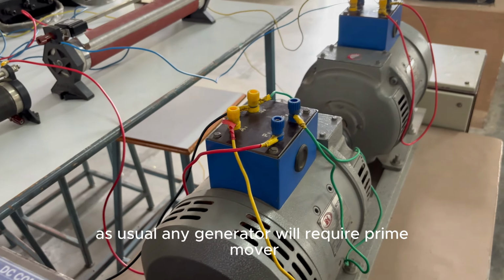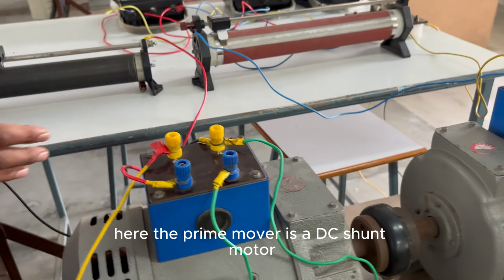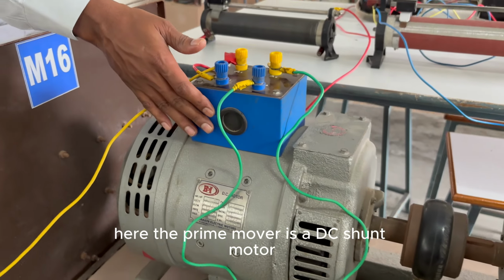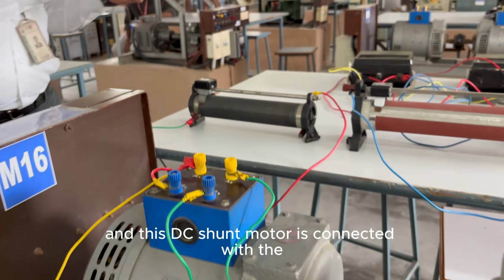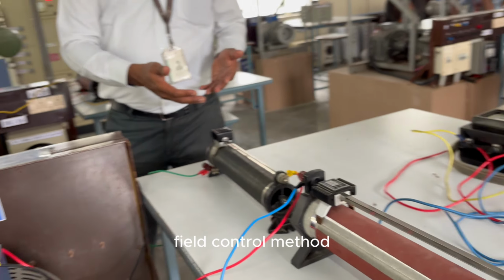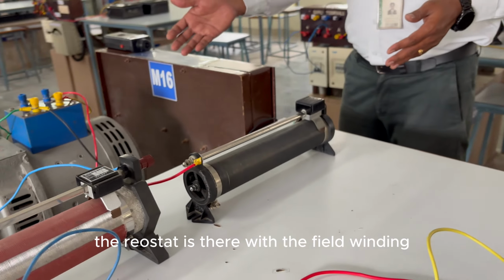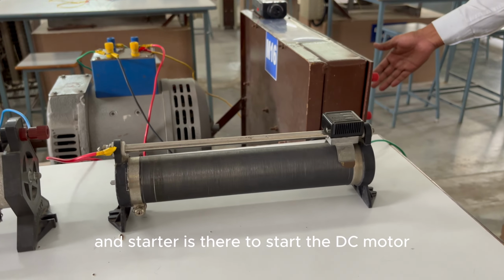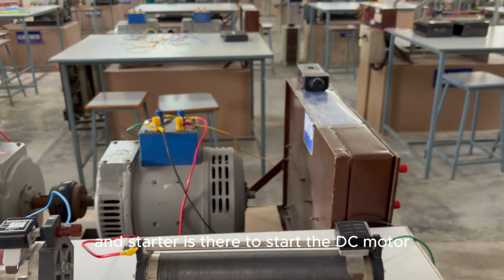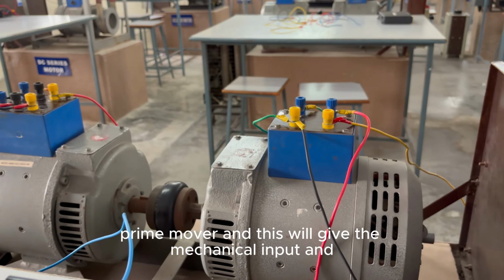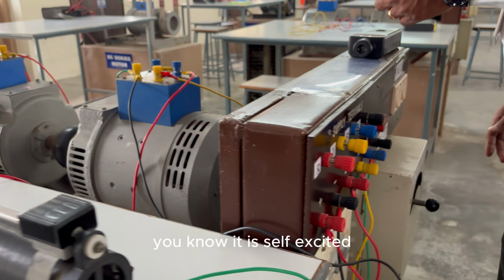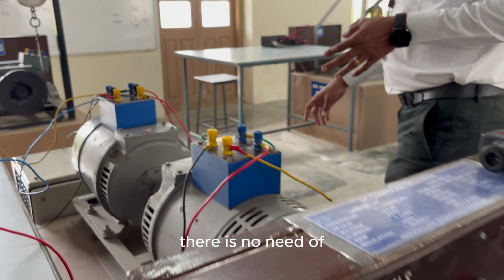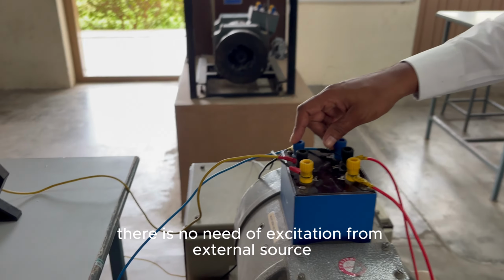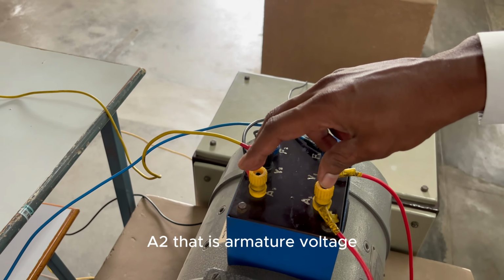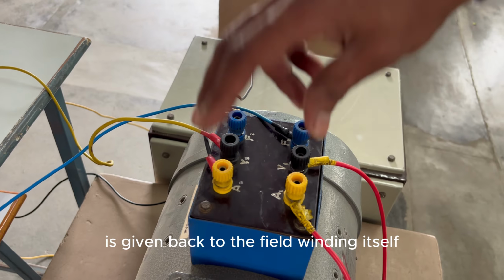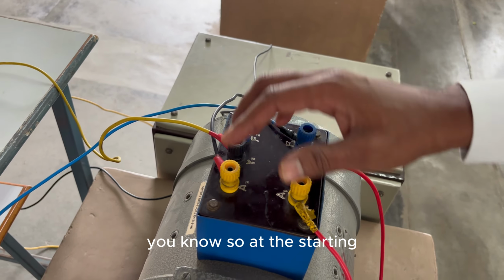As usual, any generator will require a prime mover. Here, the prime mover is a DC shunt motor, connected with the field control method. A rheostat is there with the field winding, and a starter is there to start the DC motor prime mover, and this will give the mechanical input. The generator is self-excited, so there is no need of excitation from an external source. The A1 A2, that is the armature voltage, is given back to the field winding itself.